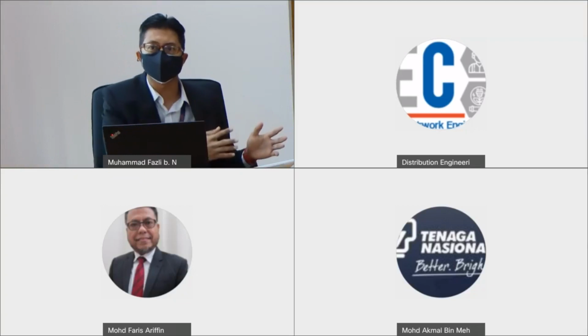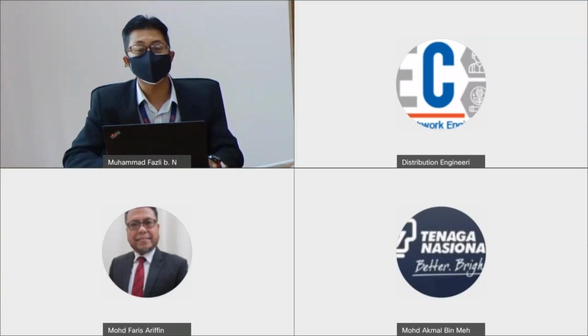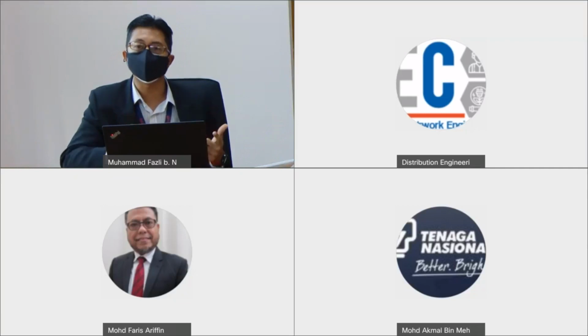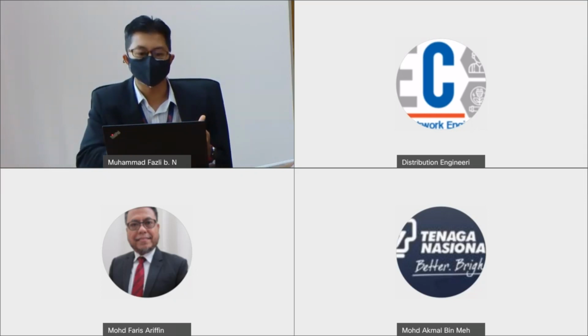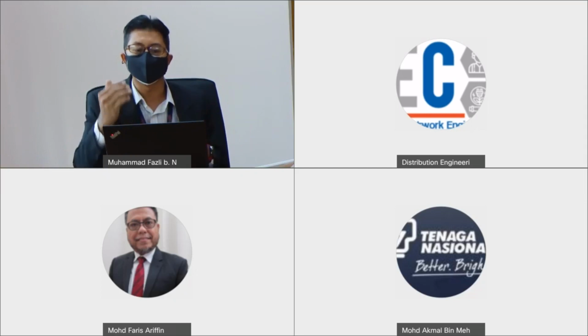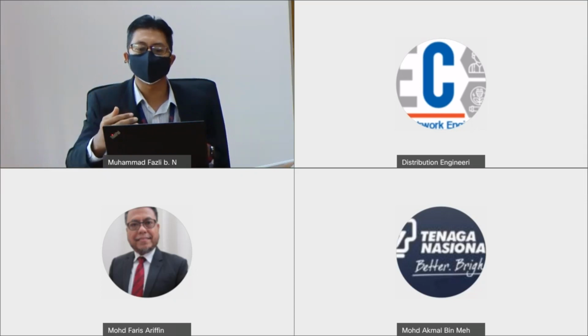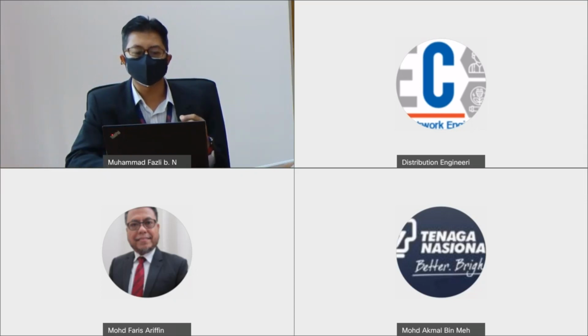Okay, guys, before I pass back to IRTS Muhammad Faris, I would like to recap what we have learned in the first part of the presentation. First, we have learned about the definition of insulation coordination, how to select insulation withstand strength, such as the 33 kV system using 170 kV. And then we learned about two types of MV bare overhead lines: number one is called shielded, and number two is called unshielded. Shielded is the bare overhead lines integrated with the earth wire on the top of the lines, and the system uses a steel cross arm. Unshielded is without earth wire on the top, and the system uses a wooden crossarm.